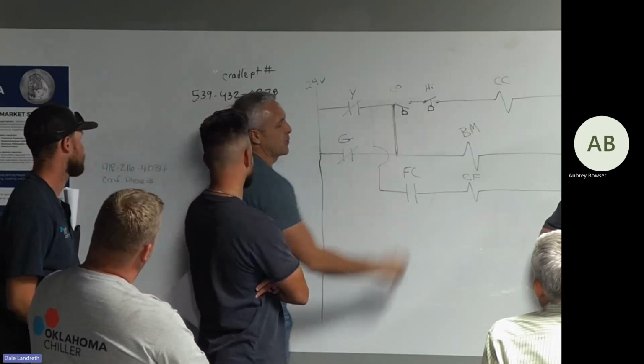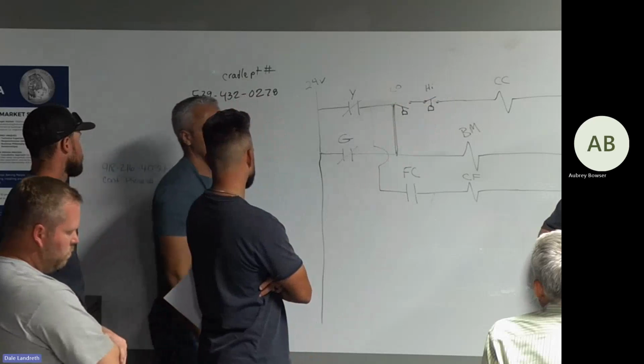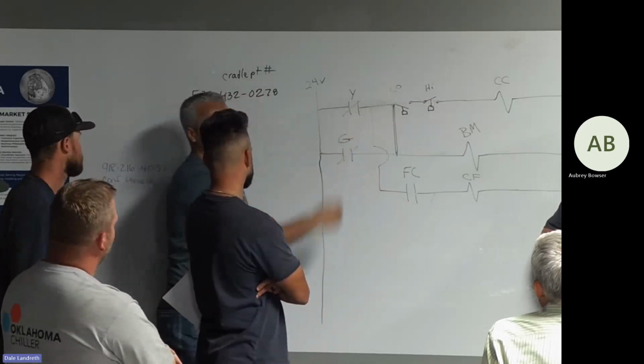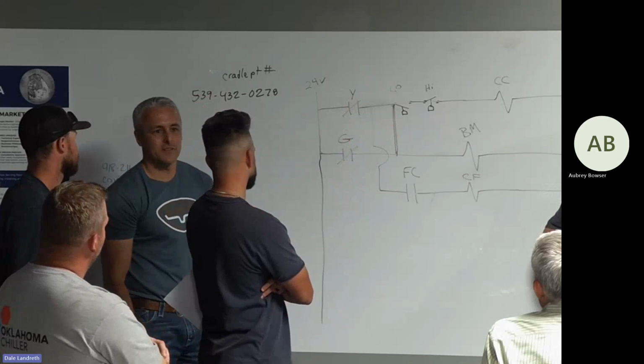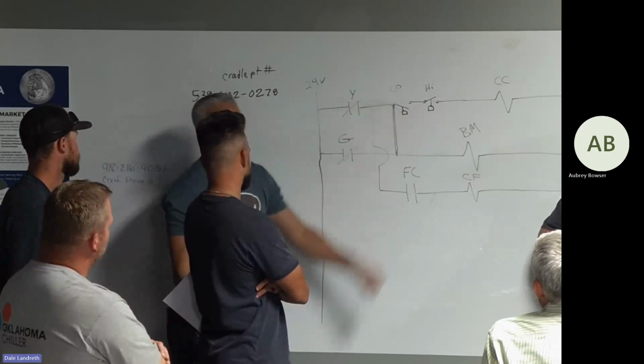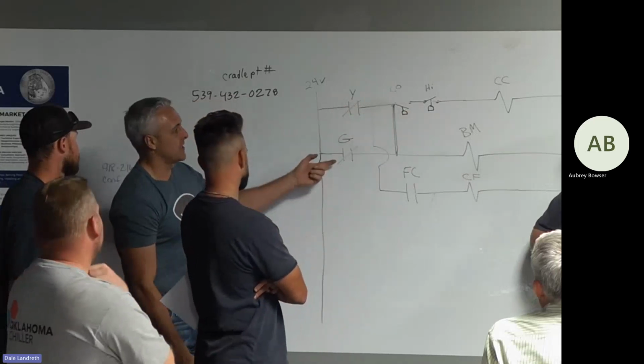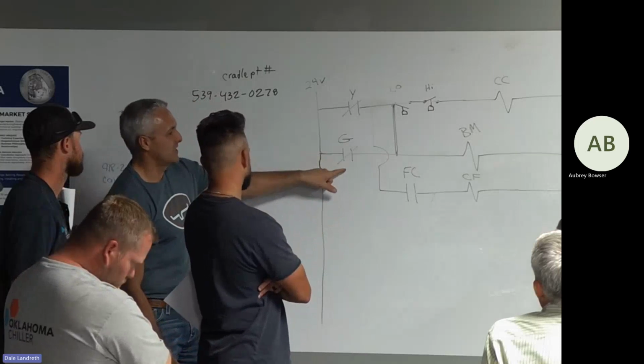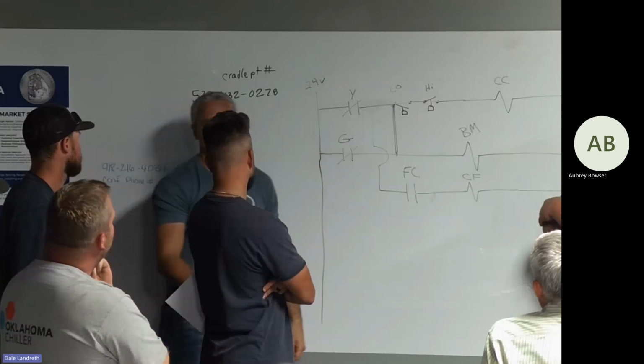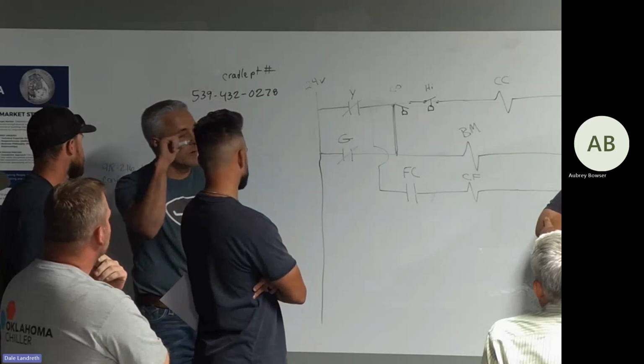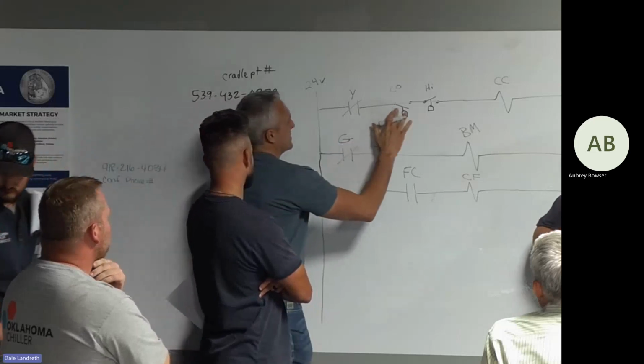You turn the G on, now the compressor's going to be running. So will the compressor ever shut off? As long as G's on, it's never going to shut off unless one of these opens up. So if you've got the thermostat set to 68 and it's 67, that compressor's still going to run because somebody wired it wrong. Just little things like that.